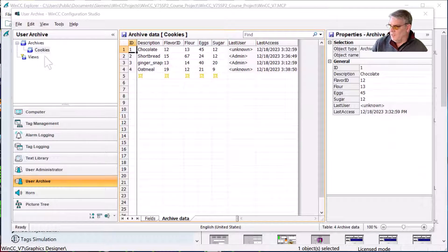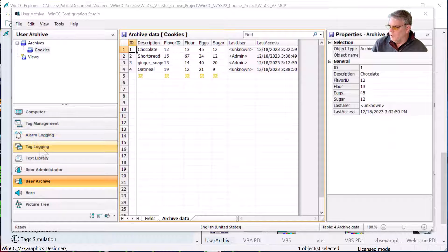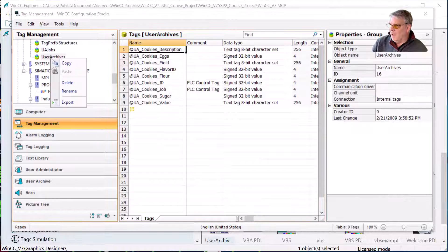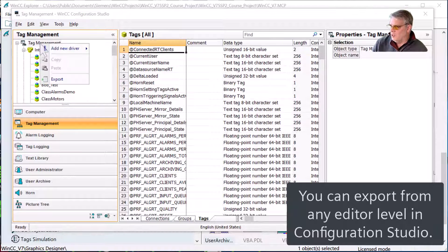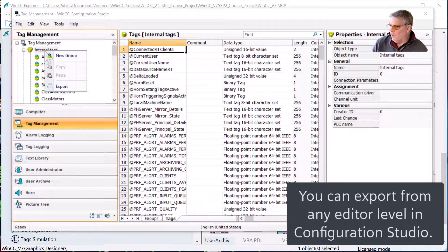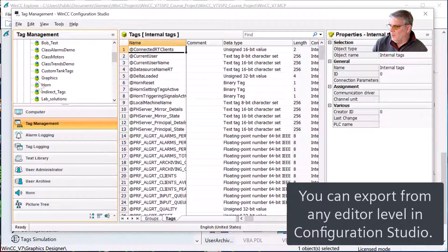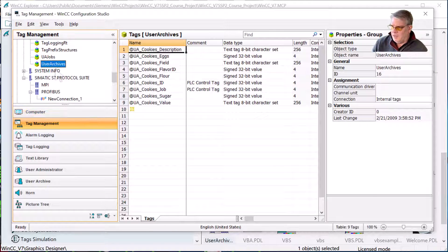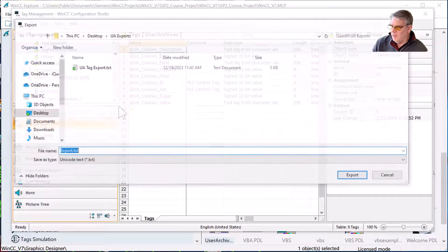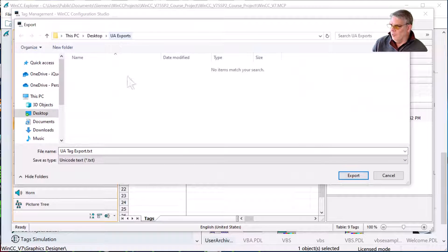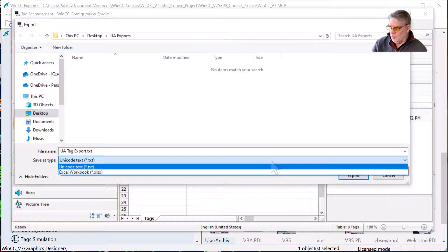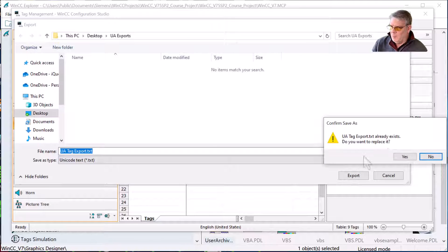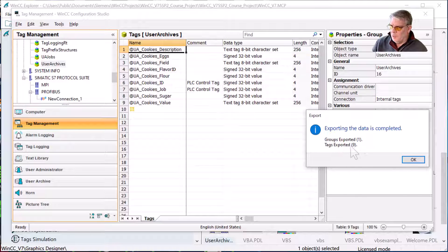I'm going to close Graphics Designer. The first thing I'll do is go into my tag management. I can just right-click on a group, a connection, or the whole thing and export whatever tags. If I wanted all the tags in this project, I would go all the way to the top and do export. The only tags I really care about are my user archive tags, so I'll right-click there and hit export. I've created a folder called UA export — this is my UA tag export. I can export it as an Excel workbook or just text. I'll leave it as text and hit export. It tells me it exported one group and nine tags.